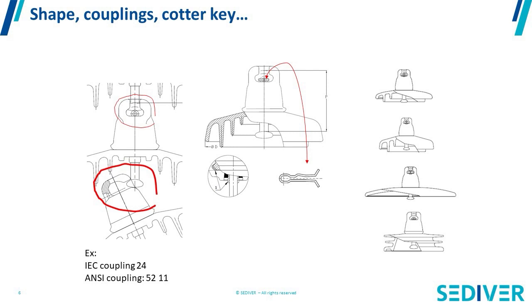But you have another style of insulator which actually was initially used in China because of dusty environments, mostly from industrial environments, but at the same time with some humidity. So you need to have something on the insulator which gives you a better protection against arcing when you have wet conditions. We'll talk about later when we will address pollution questions. But in this particular insulator you see that the ribs are outside, they are not underneath. So this outer rib insulator is actually having a long distance for the arc, which is what we call the leakage distance, but at the same time will have ribs which will clean up easily with the wind because the ribs are outside and not underneath. So you have four different names for different shapes of insulators.